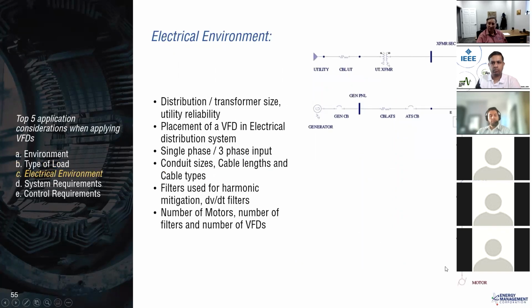We've talked about the electrical environment. One thing I didn't really mention a lot is the cable on the output of motors. You've probably seen manufacturers advertise: don't install a VFD without a VFD rated cable. It's becoming more talked about. I haven't seen a lot of real issues, and we do measure a lot, do a lot of ground resistance testing and measuring of cables and commissioning.